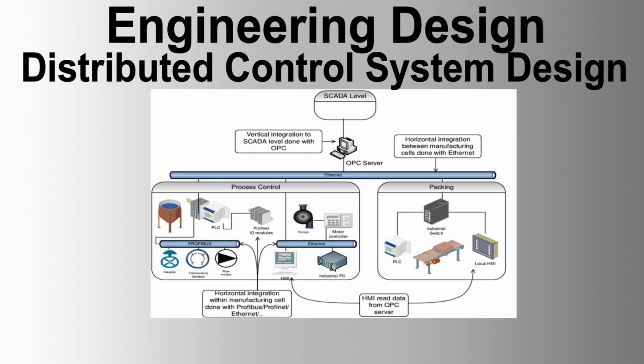7. Communication bus interface. The new DCS must be compatible with and integrated into the existing dual redundant data highway and DECnet system. Communication buses must have redundant cables routed in separate paths to avoid simultaneous failure with automatic switchover without operator intervention. The DCS must provide system status displays to monitor communication bus operations and generate alarms for bus failures. Detailed DCS grounding requirements and installation details must be provided.